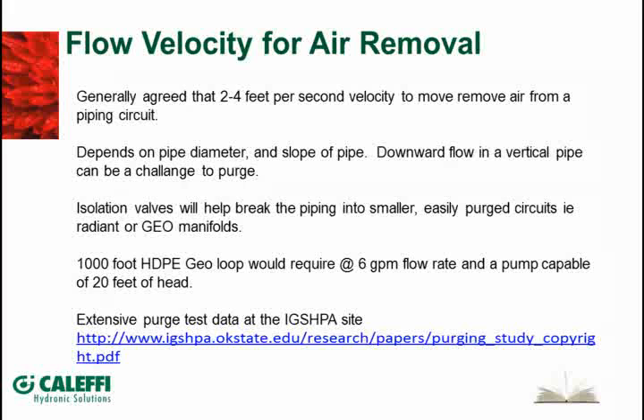The more isolation valves that you can put out at your heat emitters or at your manifolds, where you can zone or close off different loops and just do one loop at a time, that's going to help you purge the circuits. It's a time-consuming job to do this properly. And I think what happens on a lot of jobs is guys don't allow enough hours at the end of the job to do this, where you put in a chemical and you go back a couple of days later, you have to flush it out, and you have to go back and repurge all those loops. So take the time and do it right, because you're protecting the investment for your homeowner, and certainly avoiding the callbacks of a no heat call in one of the loops with an airlock or something like that.